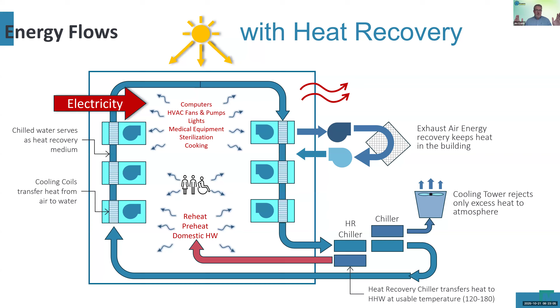Looking at this chart, the yellow or orange part represents the heating load of the building, and also the heat being taken out by the cooling system. This example is an ambulatory surgery center in Georgia, not a hospital. With a heat recovery system, we can convert as much of that removed cooling load into usable heat as needed. The orange area represents all the heat available through that process, and the red line is the actual heat load of the building.